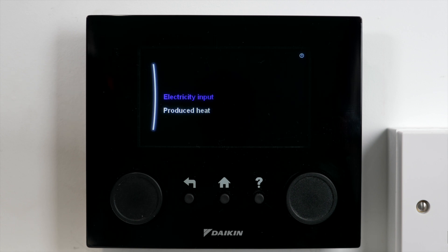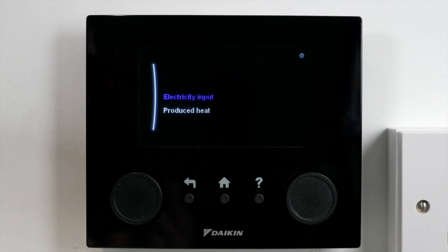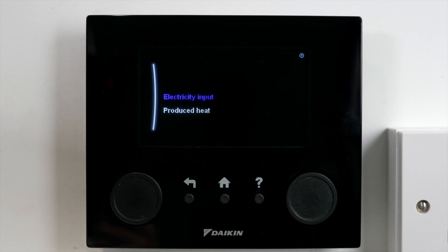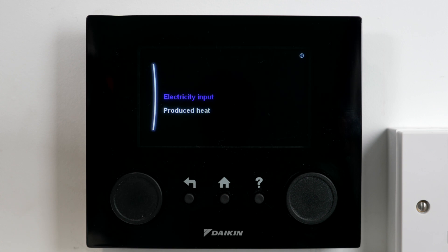Now the most important thing is your SCOP, or your seasonal coefficient of performance, and this is measured over a whole year. It's the same calculation, but how much heat we've produced in a year divided by how much electrical input we've bought and put into our system.